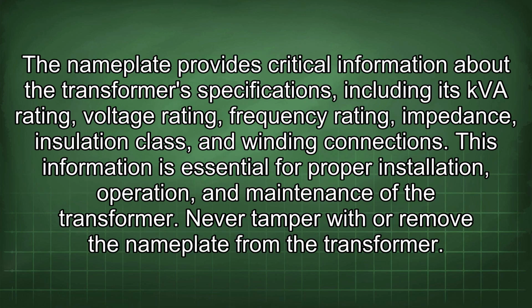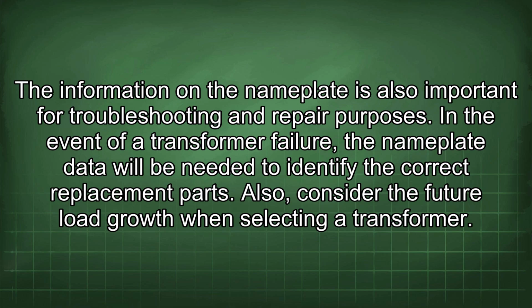The nameplate provides critical information about the transformer's specifications, including its kVA rating, voltage rating, frequency rating, impedance, insulation class, and winding connections. This information is essential for proper installation, operation, and maintenance of the transformer. Never tamper with or remove the nameplate from the transformer. The information on the nameplate is also important for troubleshooting and repair purposes. In the event of a transformer failure, the nameplate data will be needed to identify the correct replacement parts.